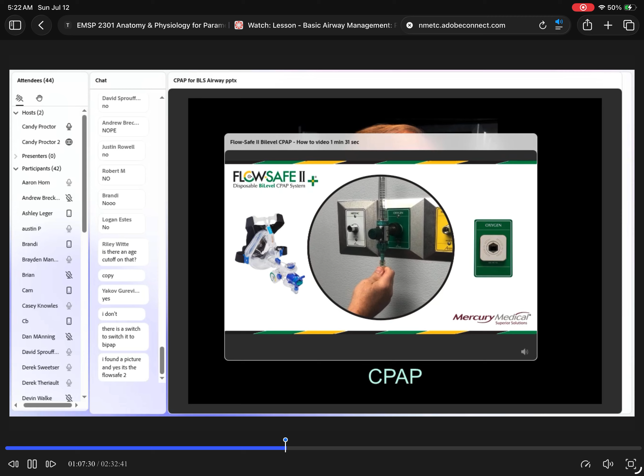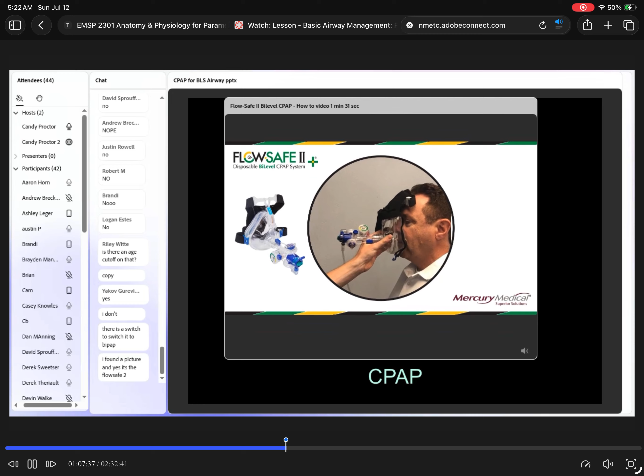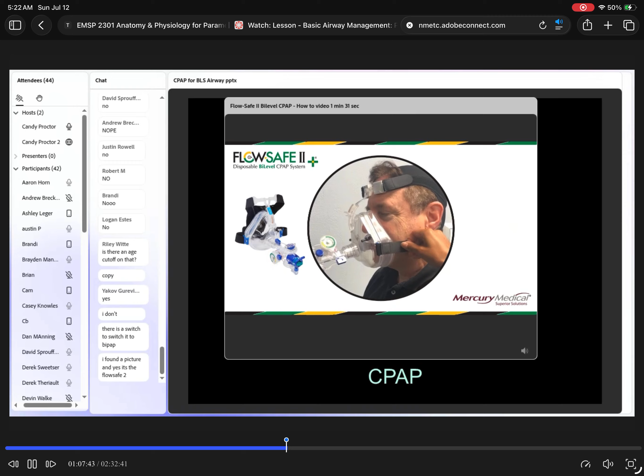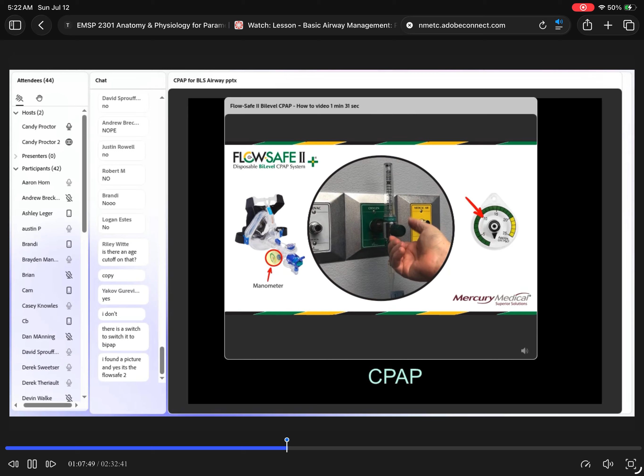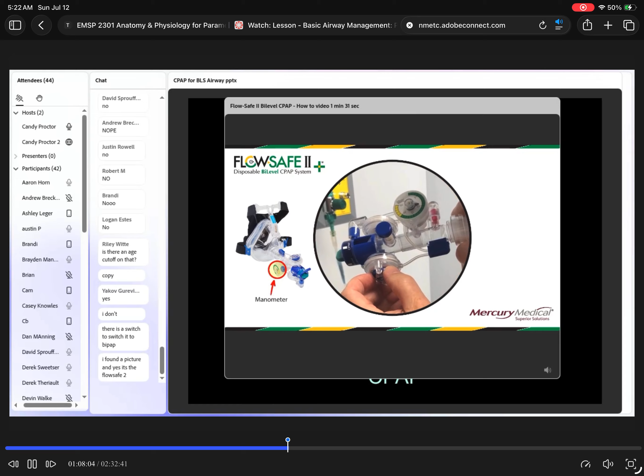Start by placing the device in CPAP mode. Then connect the oxygen tubing to a gas source. Set the gas flow to 8 liters per minute. Now apply the mask to the patient. Adjust the gas flow rate to achieve 5 centimeters of water pressure for CPAP. If the manometer does not register, check the mask seal for leaks and adjust the straps. Then, if there are no leaks, adjust the gas flow rate to 10 centimeters of water pressure for CPAP and place the device in bi-level mode. Finally, adjust the EPAP to 5 centimeters of water pressure and then use the manometer as a guide to adjust both the IPAP and EPAP.